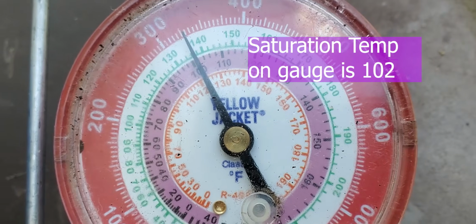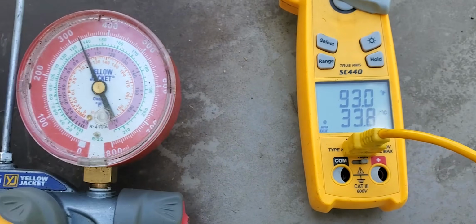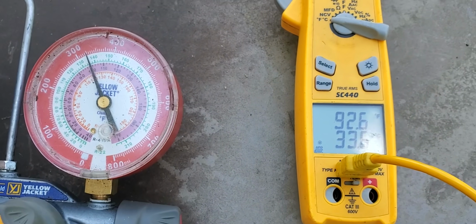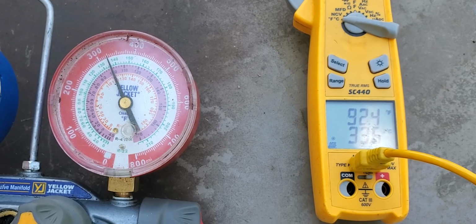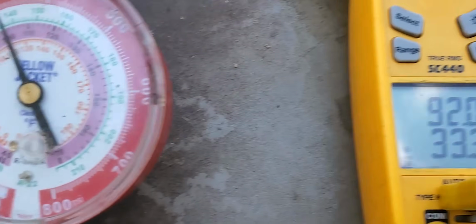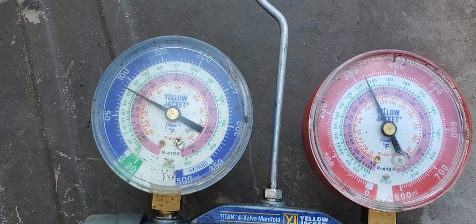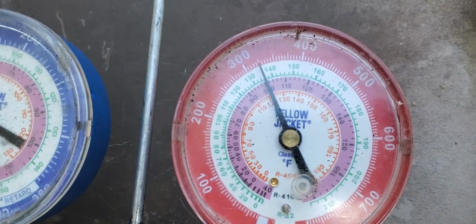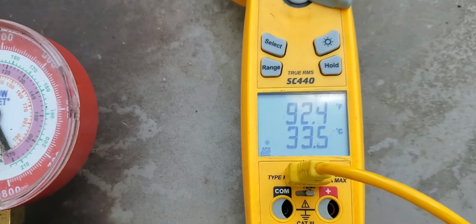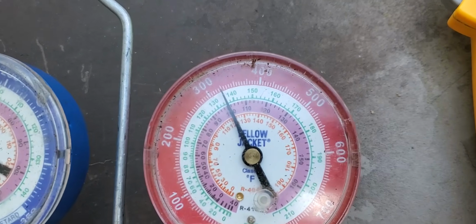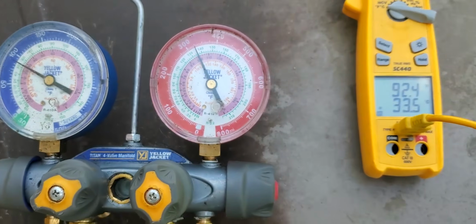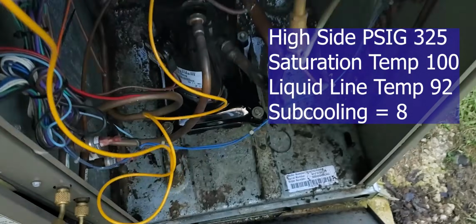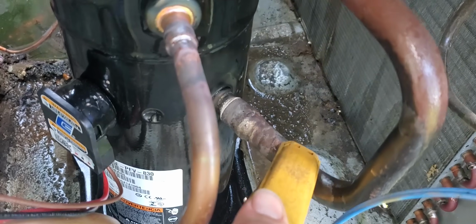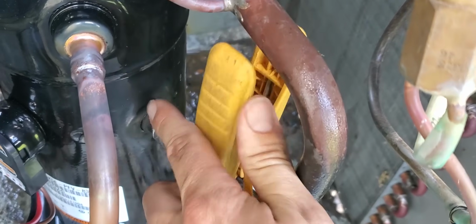Record the saturation temperature. You measure the temperature of the liquid line near the metering device. When using a temperature probe, firmly attach the probe to the pipe and insulate the probe to get an accurate reading, not affected by the surrounding temperatures. You record the liquid line temperature. So now we've recorded the saturation temperature. We've recorded the liquid line temperature. To determine the subcooling value, you subtract the measured liquid line temperature from the saturation temperature value, and that equals your subcooling. Saturation temperature minus liquid line temperature equals subcooling. Then you can look up and record the manufacturer subcooling value.